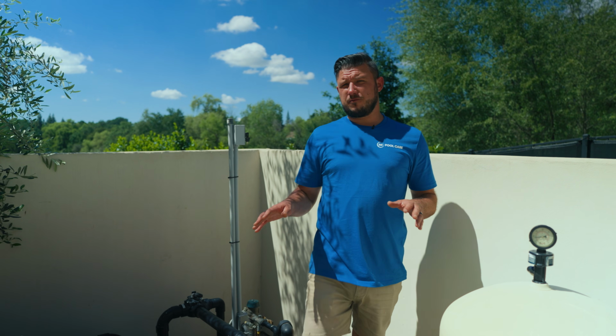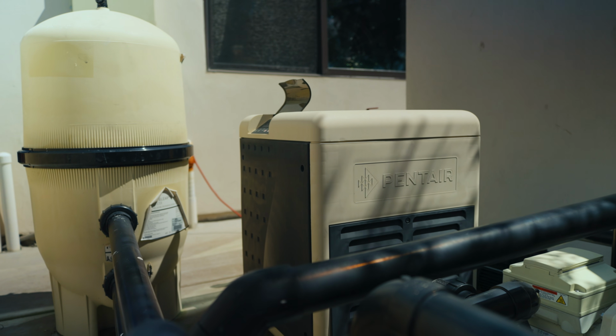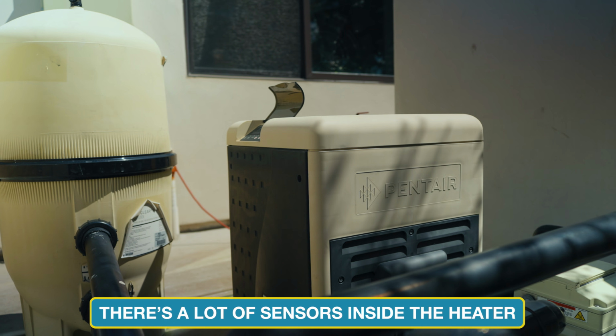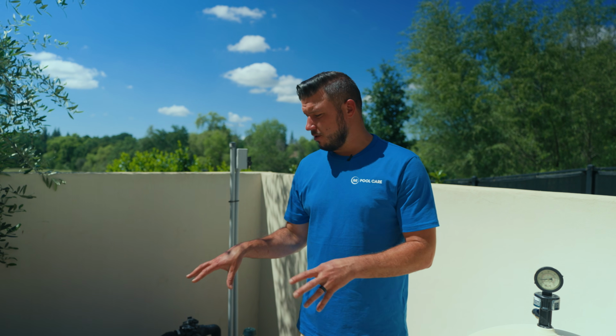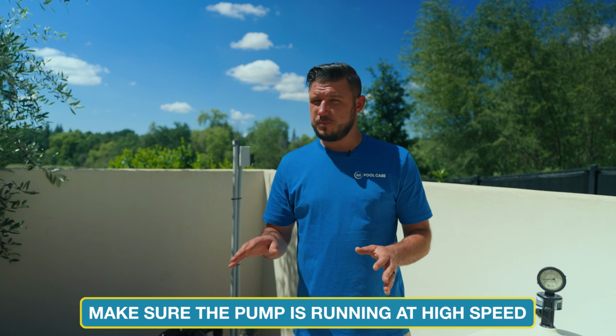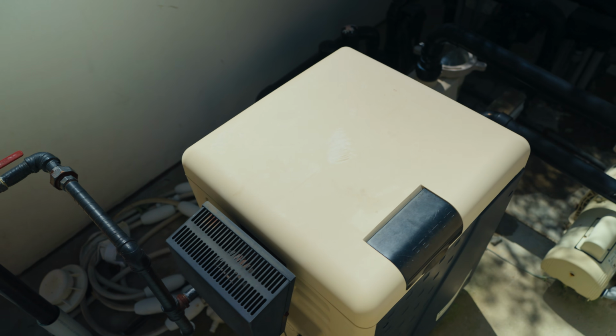Heaters are protected by the manufacturer, and the way they're protected is that there's quite a bit of sensors inside of them, and one of the sensors is a flow sensor. If the pump is not pushing enough water through the heater, to avoid the heater overheating and causing damage, there's a flow sensor. So make sure your pump is running high speed, not low speed, but high speed. That way the sensor is fully closed and the heater fires up. If the flow sensor on the heater senses that there's not enough gallons per minute, meaning not enough flow going through the heater, it will not fire up.